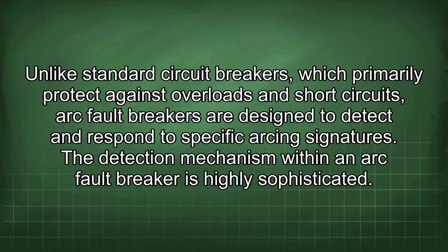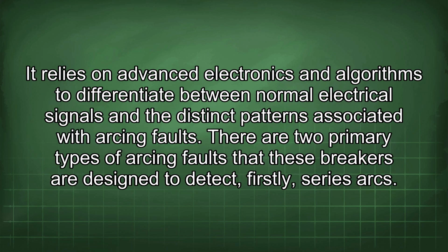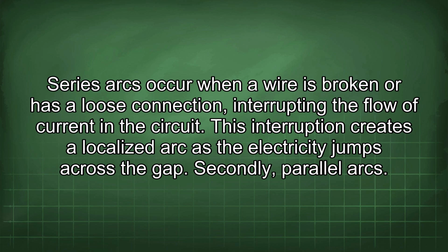The detection mechanism within an arc fault breaker is highly sophisticated. It relies on advanced electronics and algorithms to differentiate between normal electrical signals and the distinct patterns associated with arcing faults. There are two primary types of arcing faults that these breakers are designed to detect. Firstly, series arcs. Series arcs occur when a wire is broken or has a loose connection, interrupting the flow of current in the circuit.